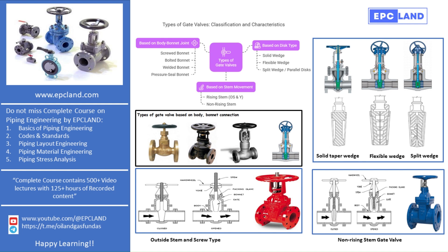The split wedge or parallel disc design uses two separate pieces instead of a single solid wedge. The two parts are held together by a special mechanism. This split design allows the disc to adjust itself to the valve seats even if one side is slightly misaligned. There is another version called the parallel disc which uses springs to keep the discs pressed against the seats. Split wedge valves are especially good for handling gases and liquids at normal to high temperatures, and they are not affected by thermal expansion the way solid wedges are.